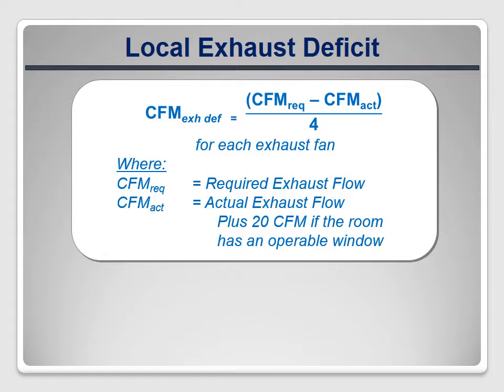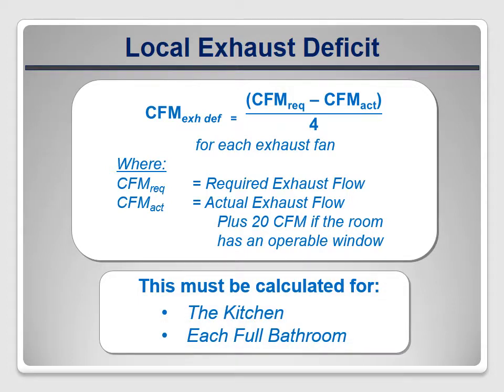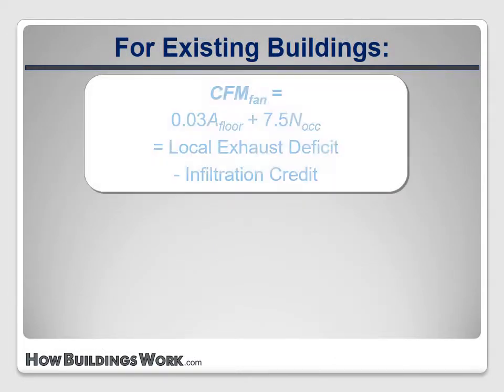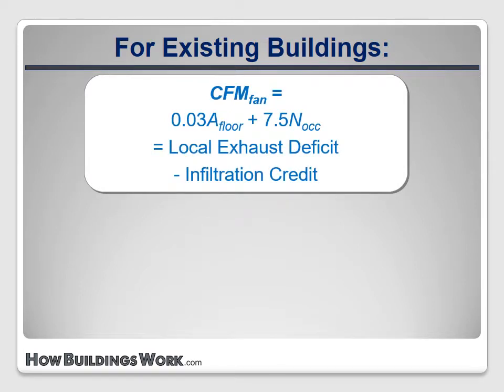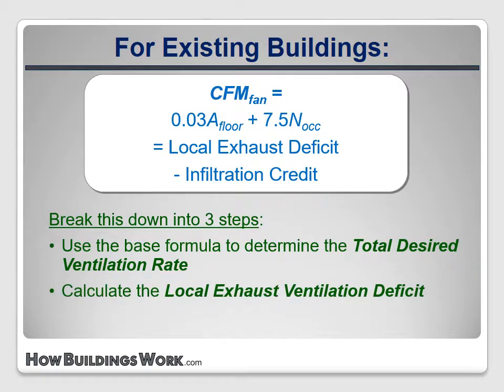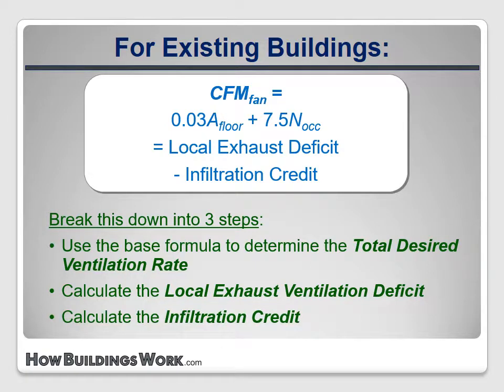This calculation must be done for each kitchen and full bathroom in the house. It doesn't apply to half baths because they don't generate any moisture. Tying this all together, we can break the calculations down into three steps: first, calculate the total desired ventilation rate using the base formula; next, calculate the local exhaust deficit based on actual exhaust flow measurements; and then apply the infiltration credit based on a blower door test result. With those three numbers, it's easy to calculate the whole house continuous CFM requirements.